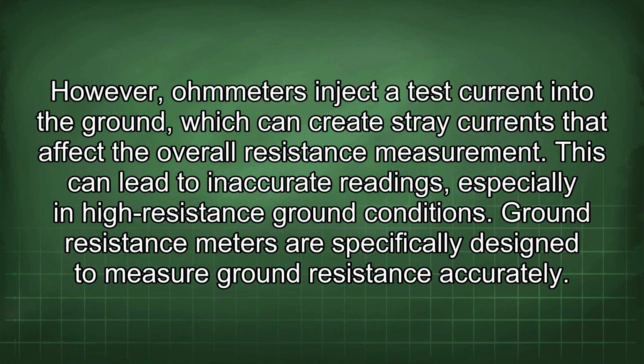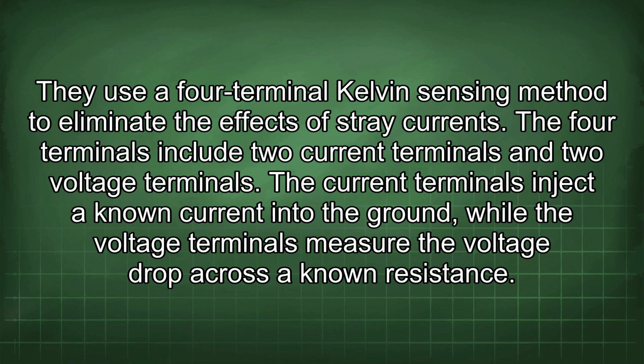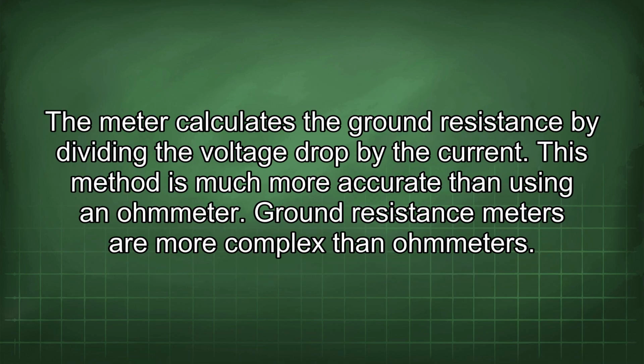Ground resistance meters are specifically designed to measure ground resistance accurately. They use a 4-terminal Kelvin sensing method to eliminate the effects of stray currents. The 4 terminals include two current terminals and two voltage terminals. The current terminals inject a known current into the ground, while the voltage terminals measure the voltage drop across a known resistance. The meter calculates the ground resistance by dividing the voltage drop by the current. This method is much more accurate than using an ohmmeter.